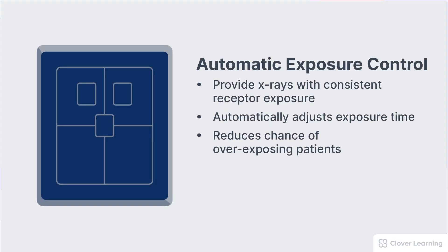AECs were developed to provide x-ray images with consistent receptor exposure, regardless of the patient size or tissue density. The AEC works by controlling the exposure time. The machine automatically adjusts the exposure time up or down to ensure the detector receives the correct receptor exposure. In other words, AEC takes the guessing out of setting the mAs, because the time and the total mAs is determined by the AEC.